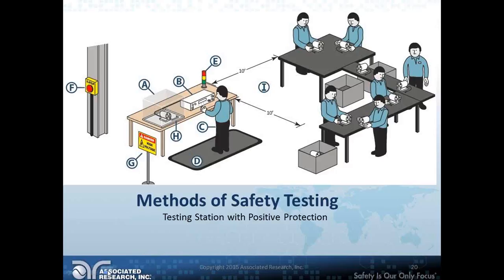I want to take a step back so people don't get confused. The 10-foot rule is about exposed conductors. In this image, there are no exposed conductors since it's in an enclosure, so technically you wouldn't need that 10-foot separation because there isn't a hazardous exposed conductor. This 10-foot rule exists within OSHA guidelines, but remember it applies to exposed conductors. If you're using an enclosure, you're in pretty good shape.